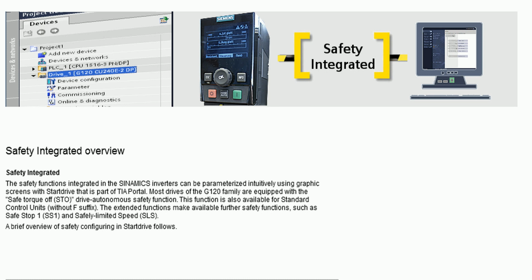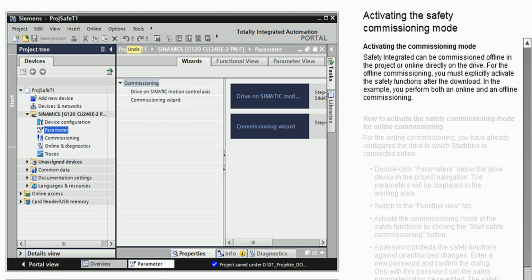A brief overview of safety configuring in Startdrive follows. Activating the commissioning mode. Safety Integrated can be commissioned offline in the project or online directly on the drive. For the offline commissioning, you must explicitly activate the safety functions after the download. In the example, you perform both an online and an offline commissioning.